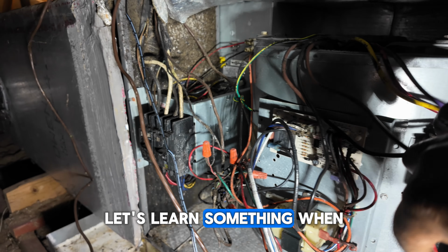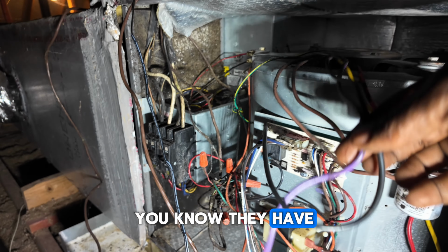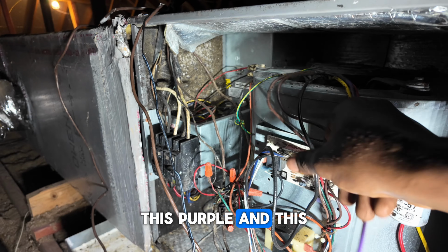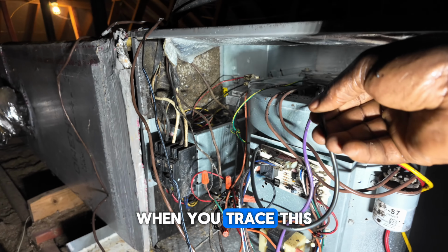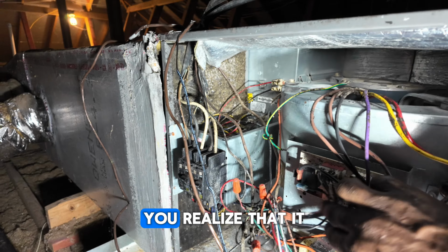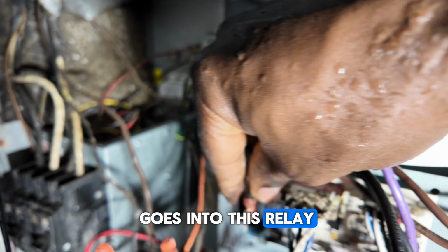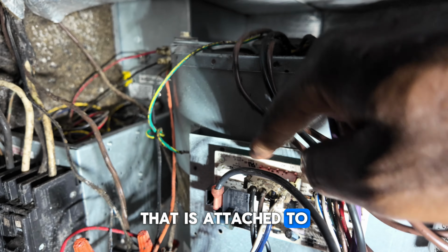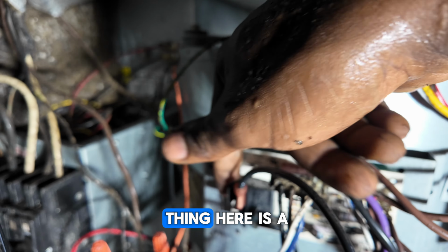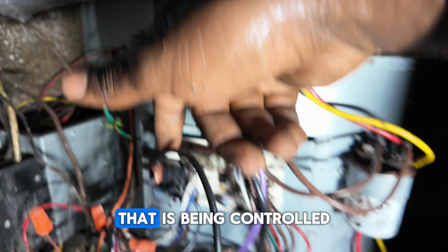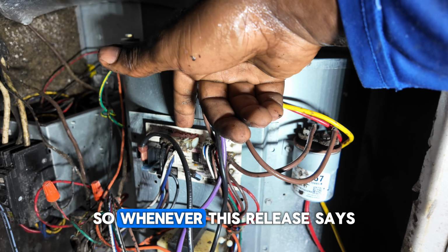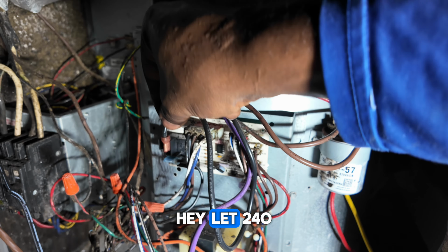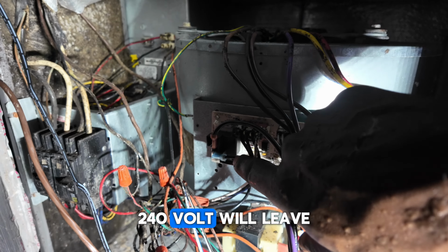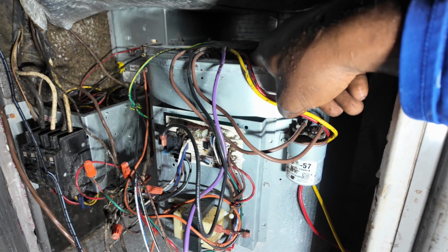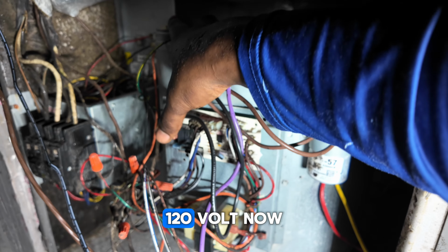Let's learn something. When you look at this motor, they have connected 2 wires, this purple and this black wire. When you trace this black wire, you realize that it goes into this relay that is attached to this board. This relay, this black thing here, is a fan relay. It is just like a switch that is controlled by this board. So whenever this relay says, let 240 volt run, 240 volt will leave from here and go into the motor. Sorry, 120 volt.